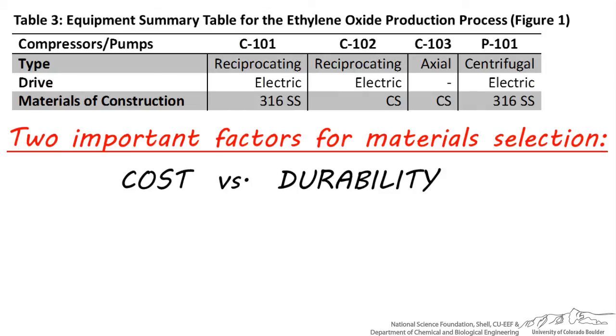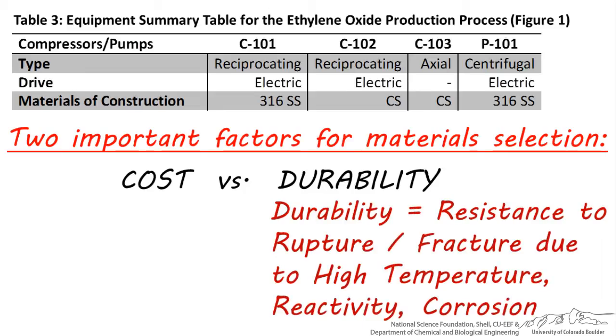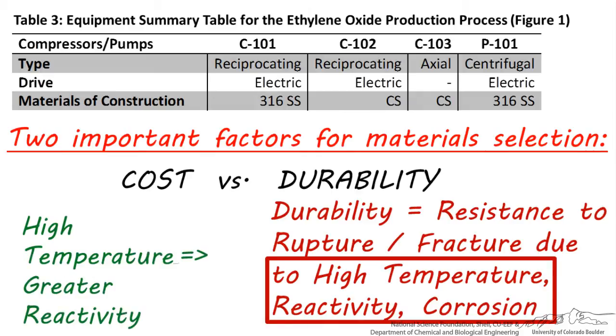We know why cost is important, but let's take a minute to talk about what durability really means. The durability of process equipment is usually determined by how resistant the material is to high temperature, reactivity, and corrosion. Pressure is usually not as important in selecting MOC, because most materials can be manufactured with the appropriate wall thickness to withstand most pressure requirements. It's very high and very low temperatures that pose more of a challenge — not only because they can compromise the integrity of the material, but also because high temperatures almost always increase the rate of reaction between components in the process stream.